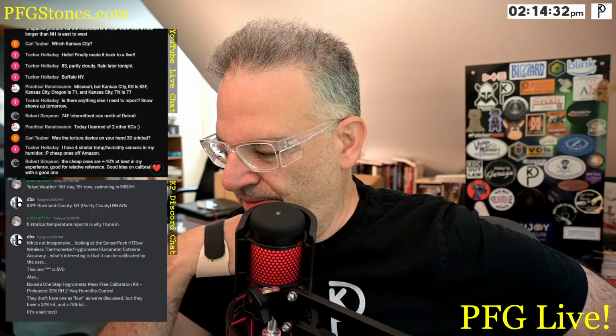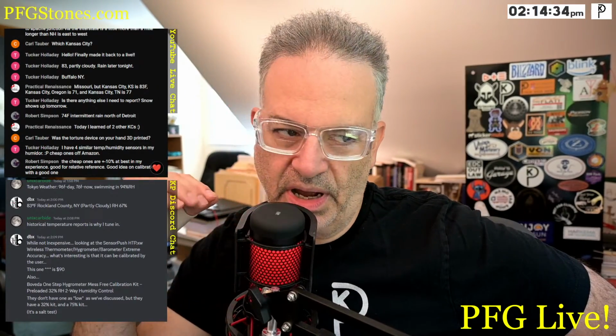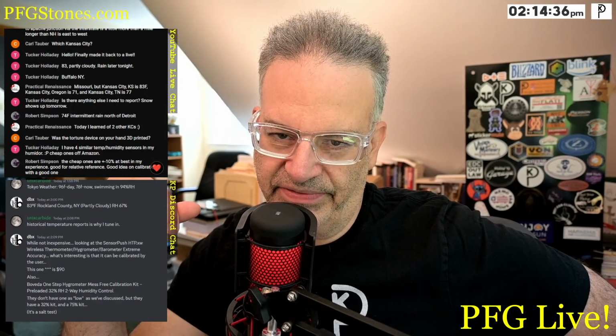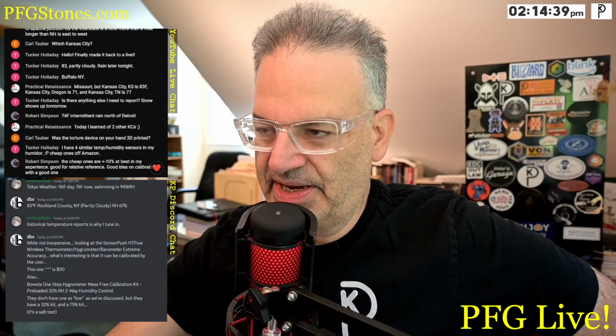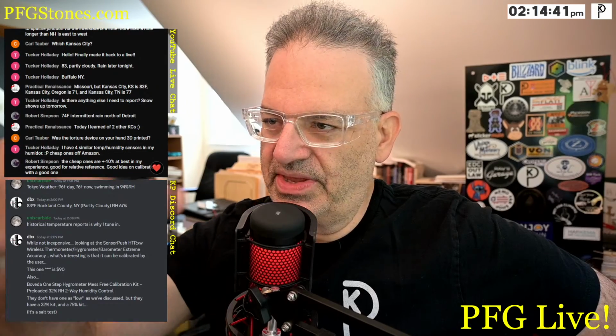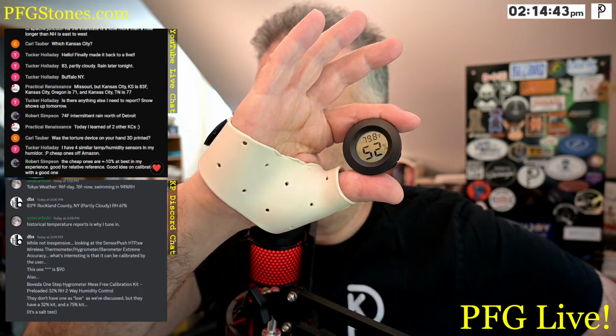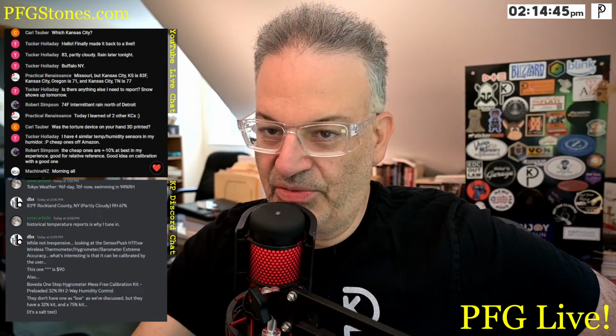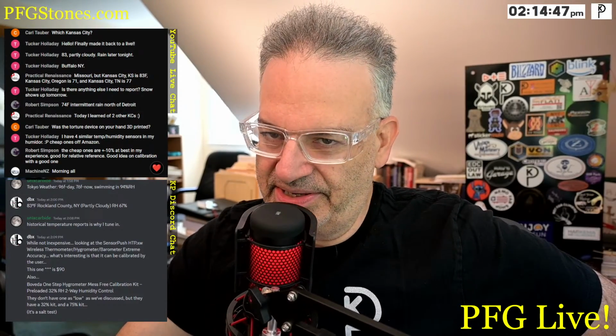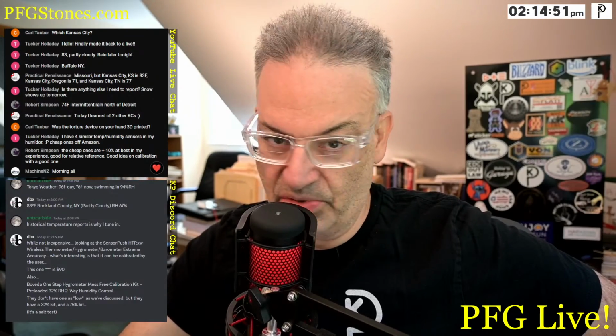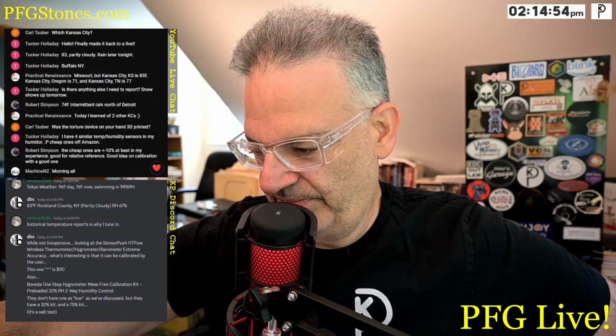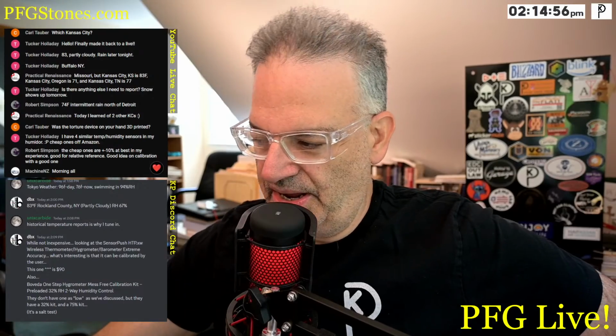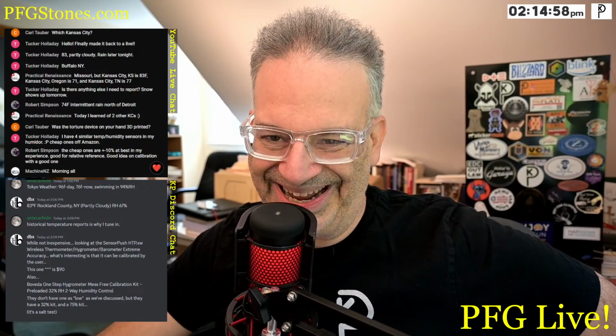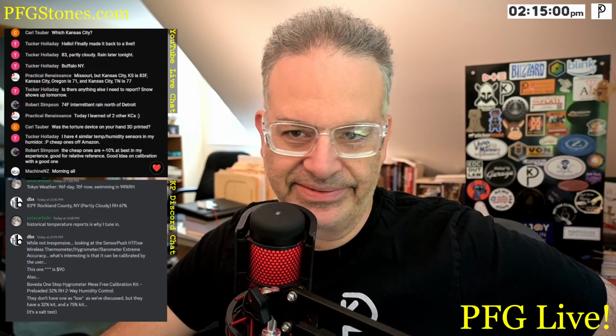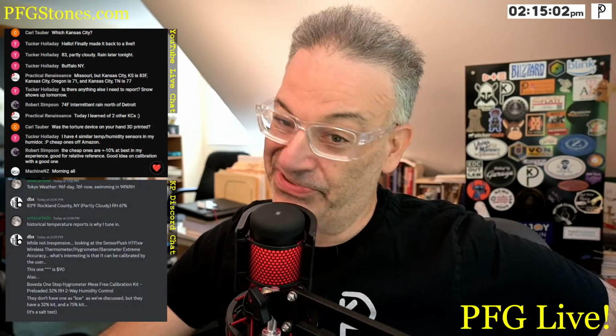So what I've come up with, well, what Doug reported to me, and then I later verified, is that when these guys say 10%, and we verified this, first of all, that's the bottom of their range. They never display lower than 10%. And we've observed them at 10%, and on the Sensorion, we're reading 18% relative humidity. So that ain't no 10% error. That's a big error.